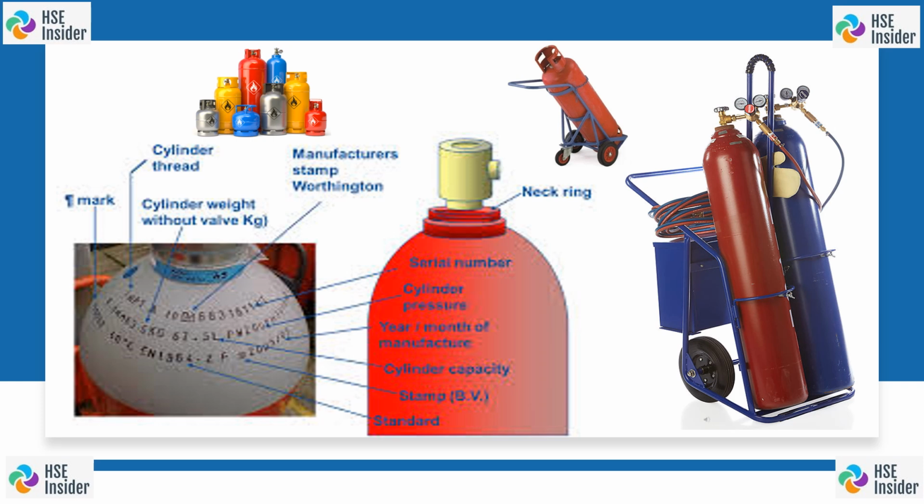Then one more, the last requirement, condemning of cylinders. A cylinder which fails to pass the periodic examination or test, or which loses tare weight by over 5%, or in which any other defect is found to be unsafe for use, shall not be filled with any compressed gas and shall be destroyed by flattening it as a whole or after being cut into pieces in such a manner that the pieces cannot be joined together again by welding.